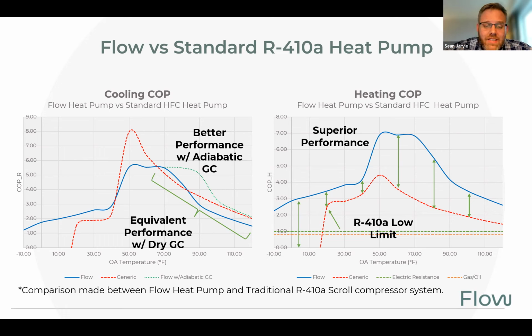The dotted green line you see here is an adiabatic misting system. Basically a little spray nozzle misting your coils with a little bit of water. Now, if we mist the equipment, it's actually more efficient than a traditional HFC system. And if you don't mist it, it's about the same, especially when you're looking at the IPLV, because they heavily weight these low ambient part load operations.